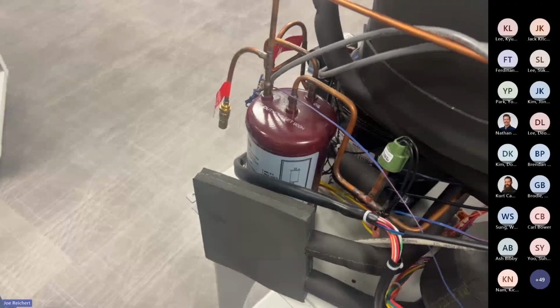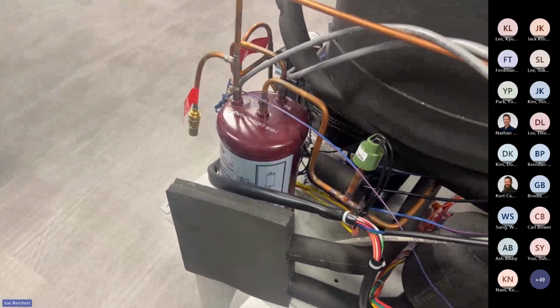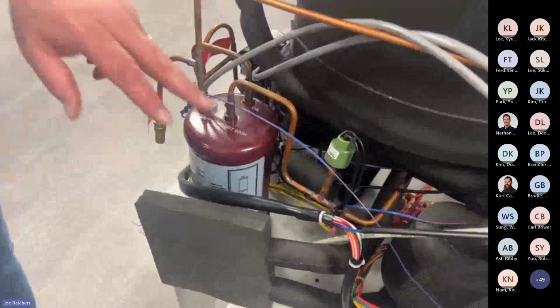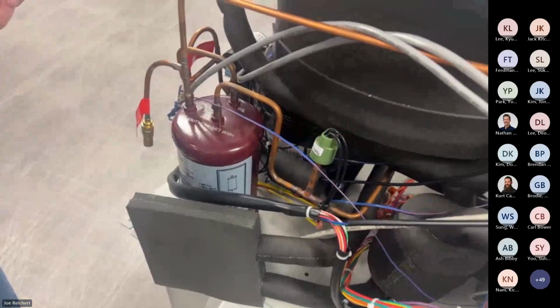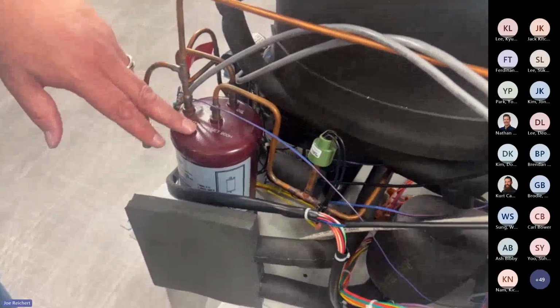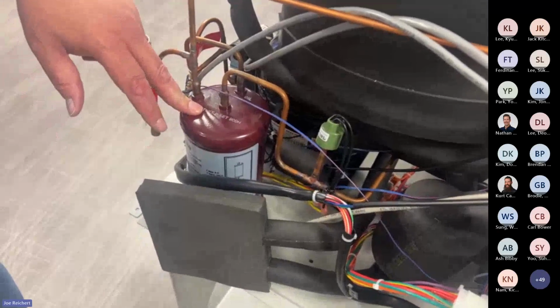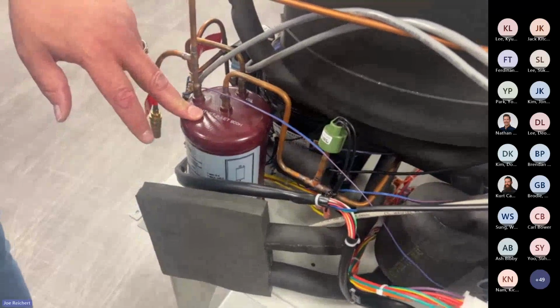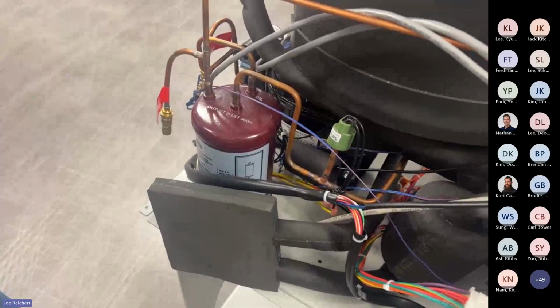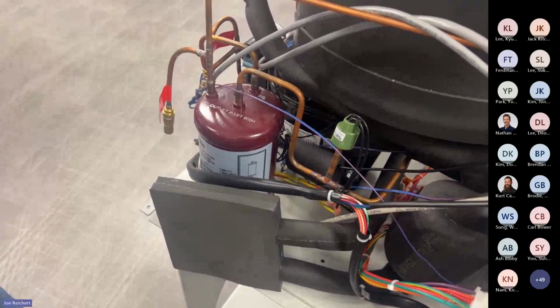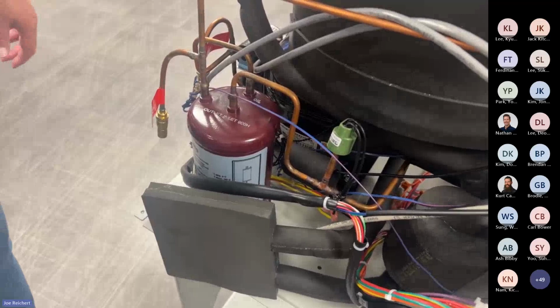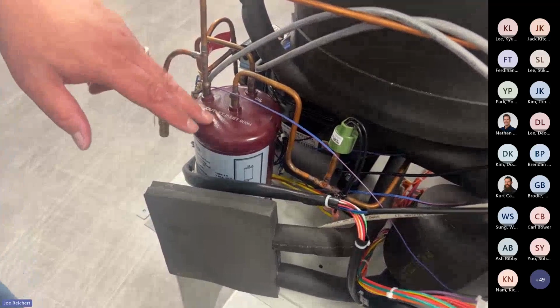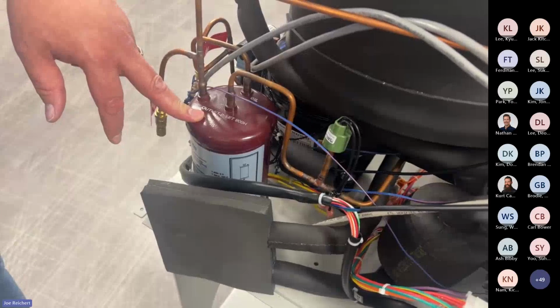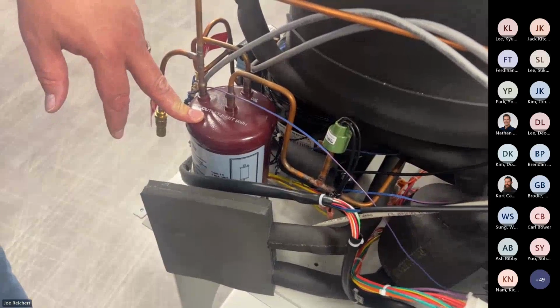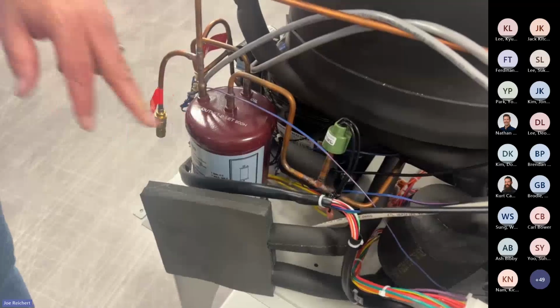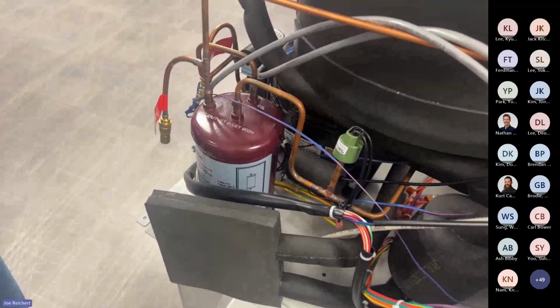You would have to make sure you add plenty of gas to make up for oil absorption, or gas absorption in the oil, with these bigger oil separators. So if you recharge a unit that has one of these oil separators, make sure you give it enough time for the gas to soak into the oil. Run the unit for several hours, turn the unit off, let it rest, turn it on, do that cycle for a couple of days actually, because it'll take a while for the gas to absorb into the oil. Once it reaches its equilibrium of absorbing into the oil, then it'll be a normal charge after that, and you'll still be able to measure your pressures.